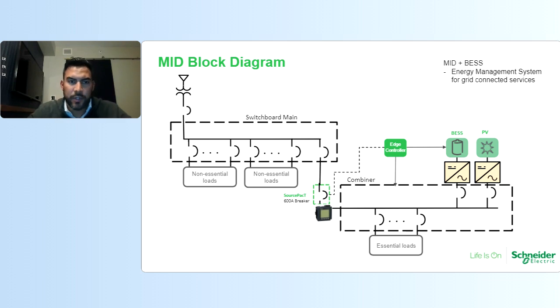So a basic main switchboard, it could be 2,000, 3,000 amps, depending on the kW rating of your energy storage system. You're sizing that correctly to your panel board. So again, you're sizing it correctly to what that full load amp output of the energy storage system can produce and attaching your essential loads there. So when you experience an outage, you're safely disconnecting from the utility, the primary service, enabling that microgrid or that energy storage system for emergency power.